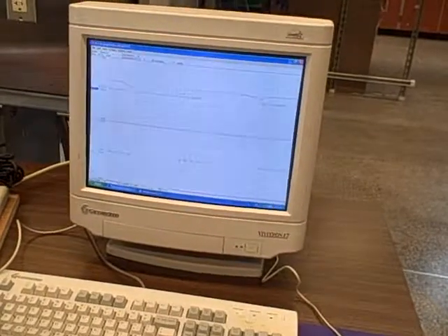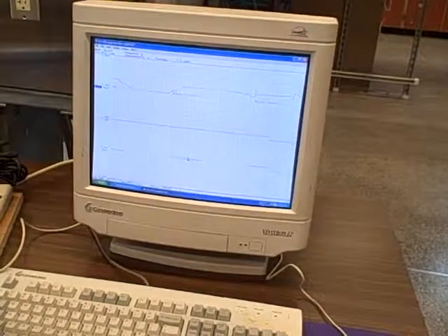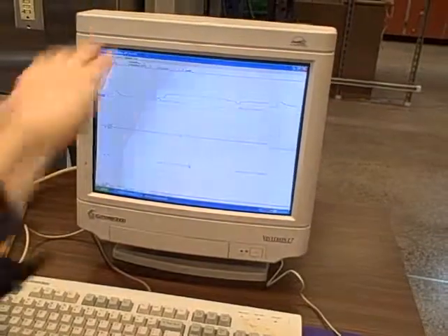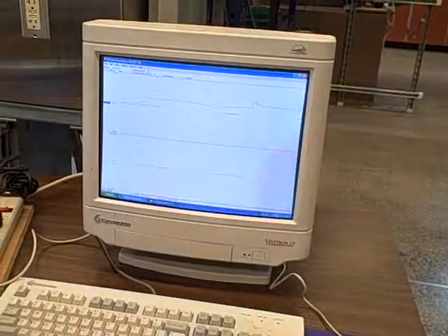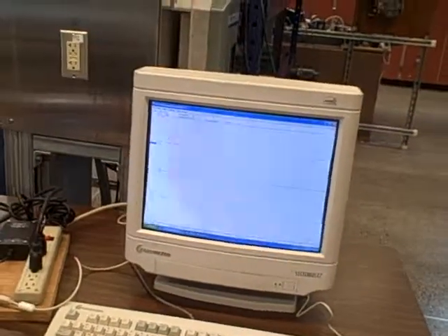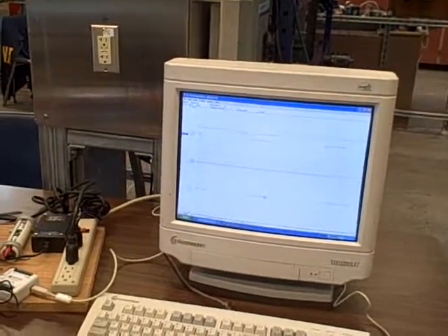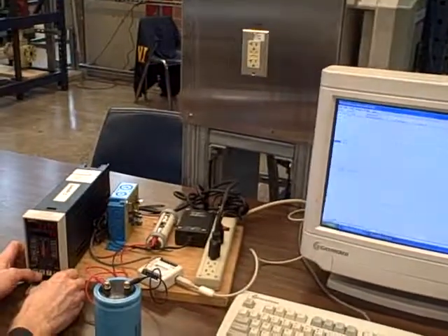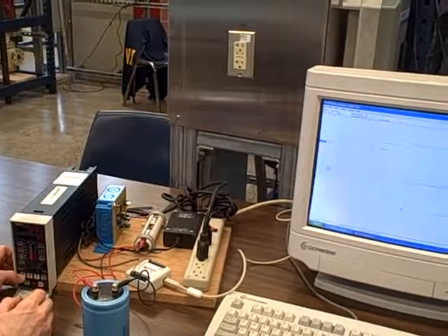When I let go of the motor shaft, it will overspeed briefly and then correct. But we don't see any undue oscillations. In fact, it looks like by the slow approach of my process variable, I can probably have an even more aggressive integral time constant. So I'm going to try this right here, cranking a little bit more integral, which is a little bit less minutes per repeat.